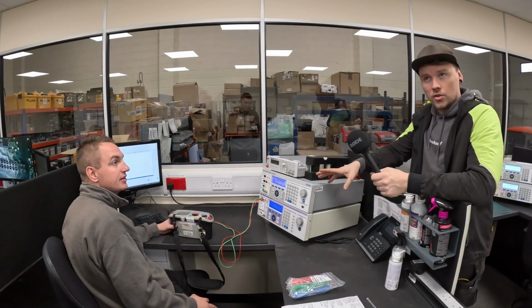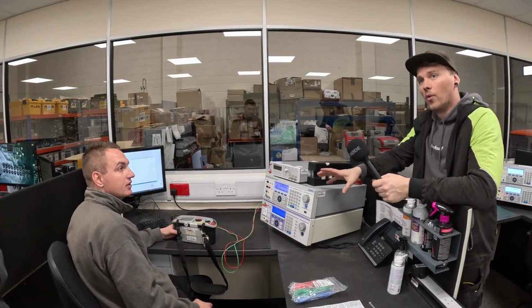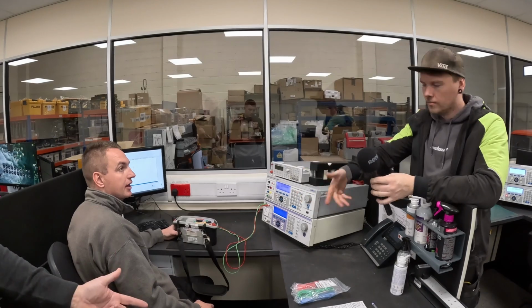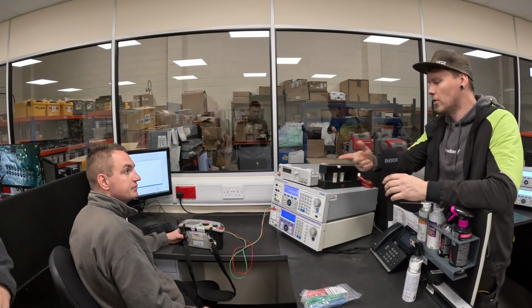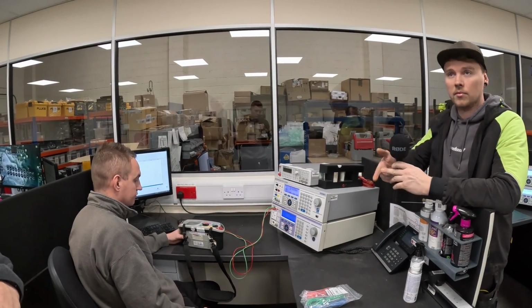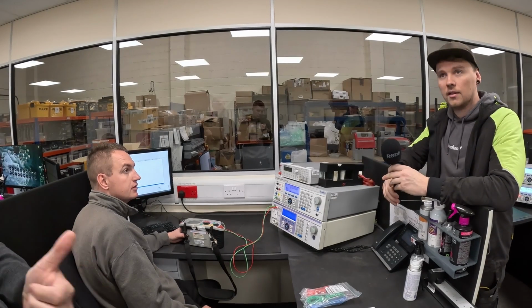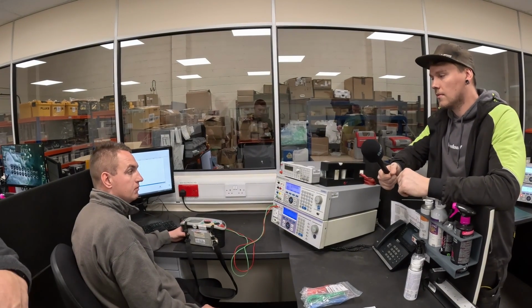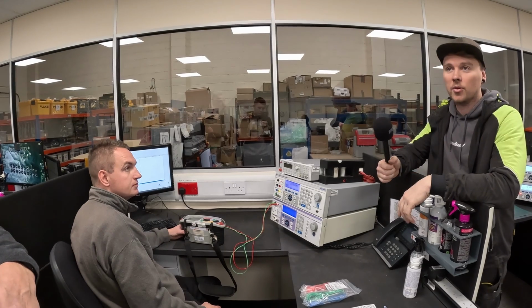That's done, and it's passed. Did you change the batteries now, or was that before? We've done that before - if the battery indicator's on, we put new batteries in, then you put your seal stamp on for the warranty. Check the fuses, make sure they're the right fuses and tight in the holders, and then that's it - elastic band stuff up, pack it away, job's done.